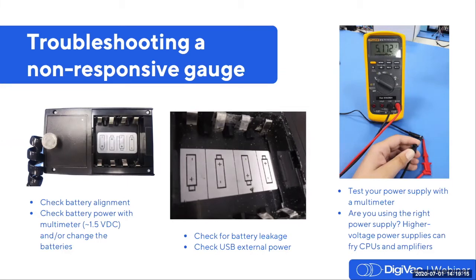But for gauges with an external power supply, such as our Model 200, 215V, and DigiVac gauges, try testing the power supply with a multimeter. Set your meter to DC volts and insert one probe into the barrel of the supply end and touch the other probe to the outside of the barrel and ensure that the supply reads the voltage written on it.